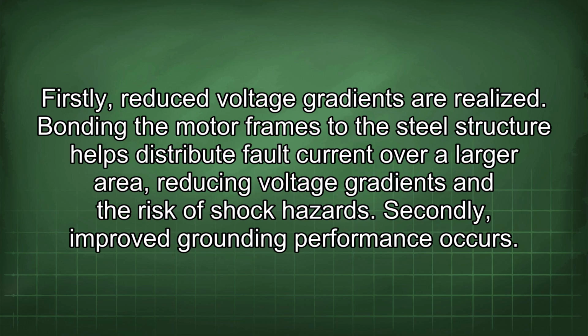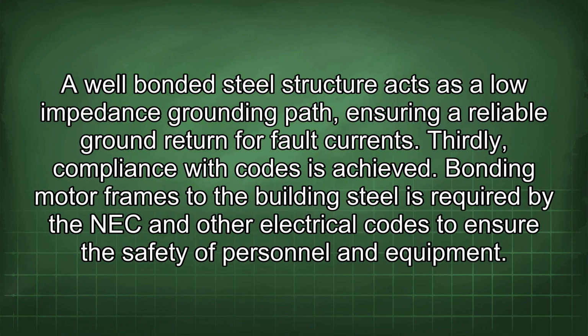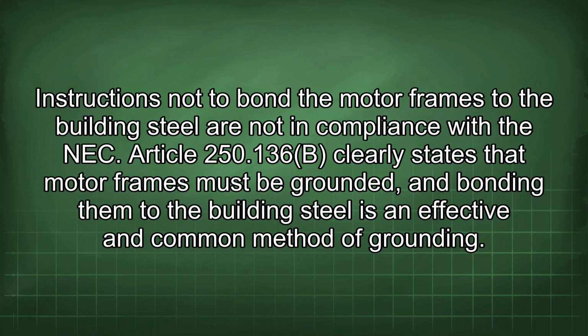Secondly, improved grounding performance occurs. A well-bonded steel structure acts as a low-impedance grounding path, ensuring a reliable ground return for fault currents. Thirdly, compliance with codes is achieved. Bonding motor frames to the building steel is required by the NEC and other electrical codes to ensure the safety of personnel and equipment. Instructions not to bond the motor frames to the building steel are not in compliance with the NEC.